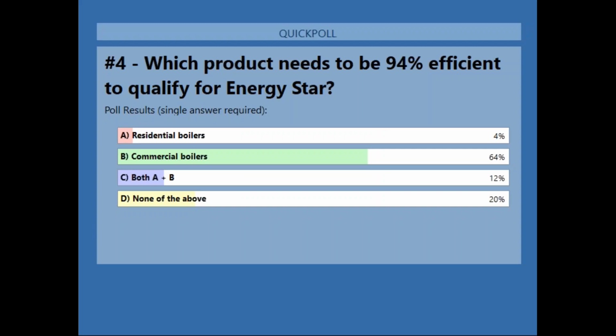And 64% of you got the answer correct. Commercial boilers need to be 94% efficient to qualify for Energy Star, plus they have to have the 5-to-1 turn down. For point of reference, residential boilers only need to be 90% AFUE.